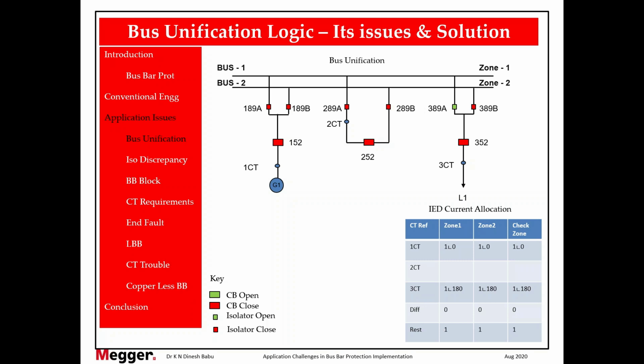What is the fundamental behind this? Let us see. Current actually flows like this, and this is a parallel path for the bus coupler. If there is a parallel path, that means current has two ways to flow. So maybe 40 to 60% would flow here, and 40 to 60% would flow here. It's not exactly 50-50 because that depends on the internal resistance of the path. So only 50% of the current is flowing here. That means the bus coupler CT is reading the wrong current, and here there is no CT to read the current flowing here. So how can we use this wrong current in our differential calculation? So the first point is to eliminate the CT from all the zones because it's giving wrong input. So we eliminated it from all the zones.